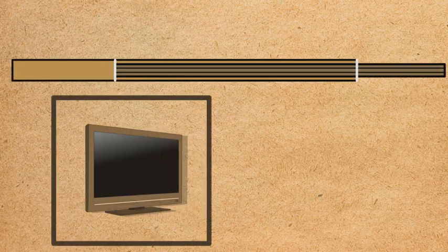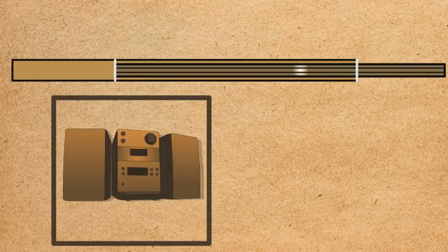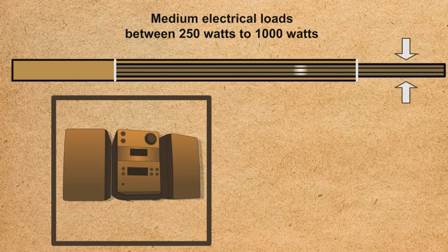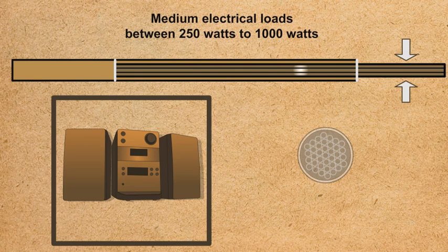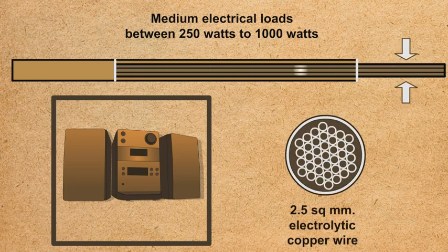Appliances like TV, refrigerator and music system carry loads between 250 and 1000 watts. These require 2.5 square millimeter electrolytic copper wire.